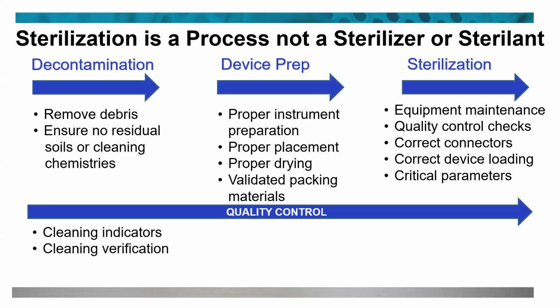But most of these items are being washed manually. Are we checking them on the clean side for any kind of cleaning verification, any residual protein or anything on there? That's something that we need to look at, because that is one of the AAMI indicators.